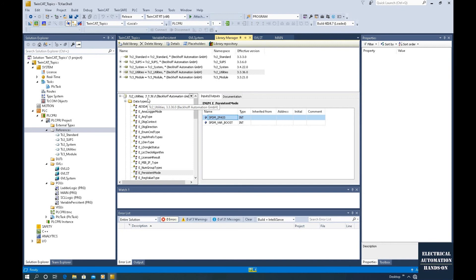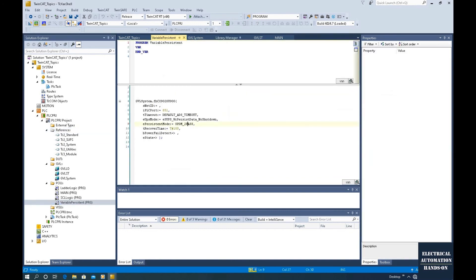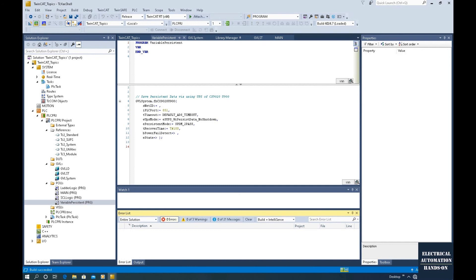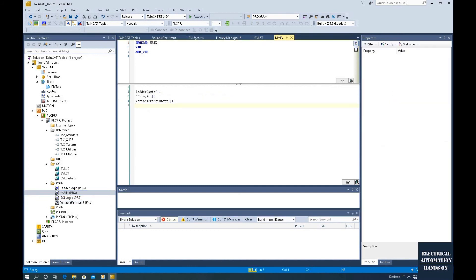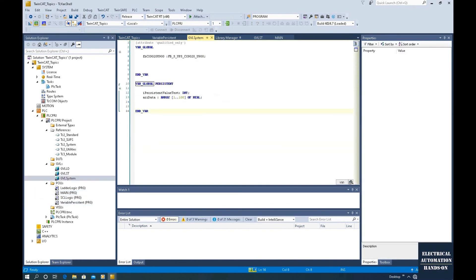So from References, we need to add TC2_Utilities. We can also add a comment — U900. As we can see, to use this function block, we do not need to trigger it with a rising edge. We just need to call it from Main, and that's it. Next, I will show a simple demonstration. I will use the persistent variable test tag, type in data, and then cycle power on the actual controller. You will see that the value — for example, 45 — will stay in this persistent value test tag and will be retained.